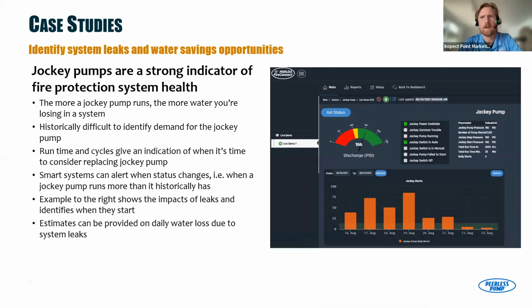Cool. Hey, Travis, got two questions. Go for it. Not pertaining to this, but one from Jim. Is the pump performance adjusted for speed when plotting that against the shop test? Great question. So that's why we actually prefer to load in the field test curve as opposed to the factory curve. We're not using a tach right now to actually look at live speed. So if we use the field test curve, that is in essence the field performance that you're looking at, and then we can use that as our barometer for comparison as opposed to the factory curve. Gotcha.